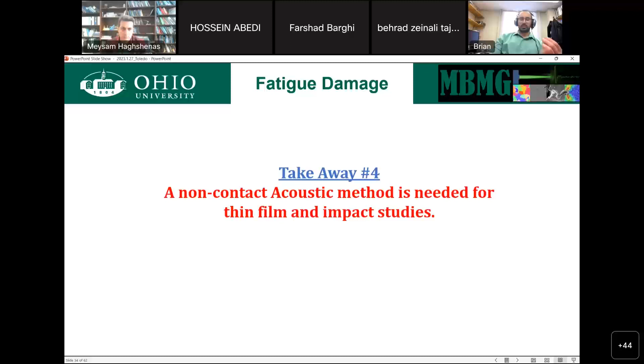What's nice about this methodology is that the laser, depending on which one you acquire, will capture a larger range of frequencies than any traditional sensor can. With a traditional sensor, you can get some that are considered wideband that reach maybe 100 kilohertz to 2 megahertz. There are some that can go a little more than that. But the laser, the one that I'm using, can go from almost 0 hertz up to 24 megahertz.